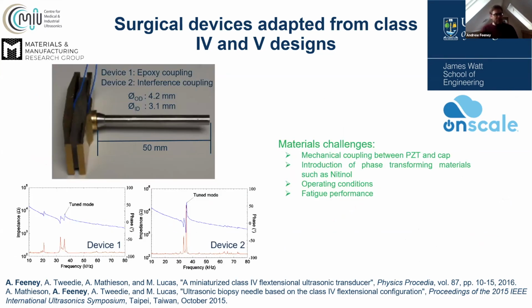I looked at 2 different coupling methods. What I mean by that is how the vibration and the oscillation of the piezoelectric material translates to the vibration and operational performance of the device. So one method was by using epoxy resin to sandwich everything together, and the other method was using interference coupling.